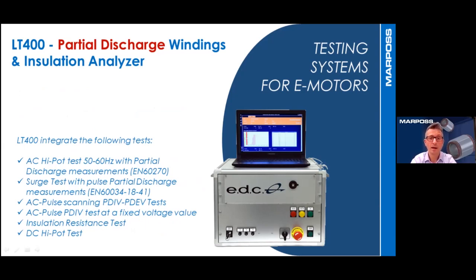LT400 performs high voltage tests. We have an AC generator 50-60 Hz in order to perform hi-pot test, and in addition we can measure partial discharge. A pulse generator in order to perform surge test, and in addition, partial discharge measurement.